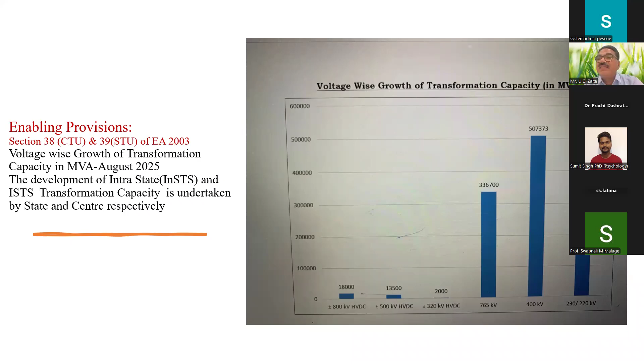And thereby the substations also. Here the losses are, you see, when the voltage increases the current reduces, and vis-a-vis the I square R also gets reduced substantially. 400 kV network is around 5 lakh, and then for 220 and below, that is 132 kV, it is around 5 lakh MVA.